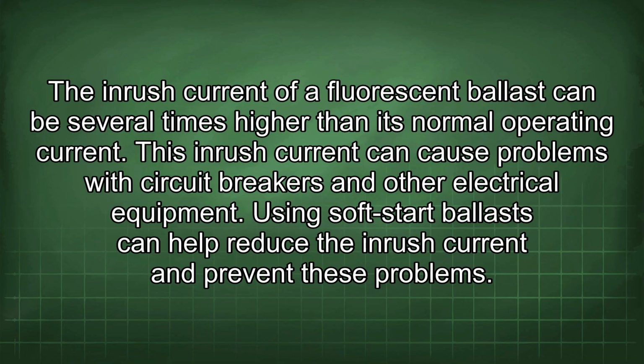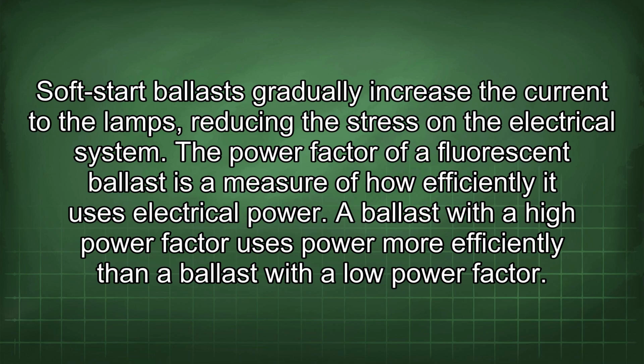The inrush current of a fluorescent ballast can be several times higher than its normal operating current. This inrush current can cause problems with circuit breakers and other electrical equipment. Using soft-start ballasts can help reduce the inrush current and prevent these problems. Soft-start ballasts gradually increase the current to the lamps, reducing the stress on the electrical system.